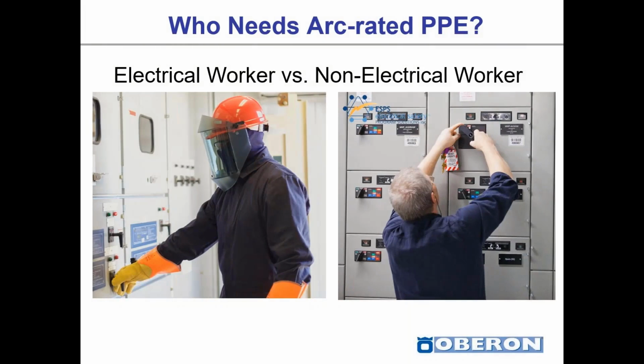Who needs arc rated PPE? Well, we have electrical workers in the industry, and we have non-electrical workers. Non-electrical workers are not permitted to be performing energized electrical work. Therefore, they do not need any arc rated PPE. Electrical workers would if they're doing the typical work tasks that are considered energized work tasks, such as testing and troubleshooting.